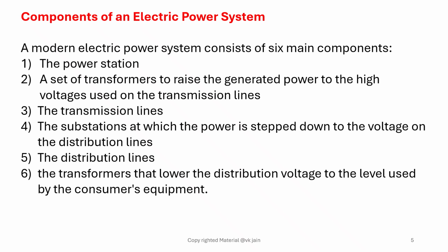Friends, let us know the components of an electrical power system. A modern electrical power system consists of 6 main components: the power generation station; a set of transformers to raise the generated power to a high voltage used on transmission lines; then high voltage and extra high voltage transmission lines; then the substation at which the power is stepped down to the voltage on the distribution line; next, the distribution lines at high voltages; and next, the transformers that lower the distribution voltage to the level used by the consumer's equipment.